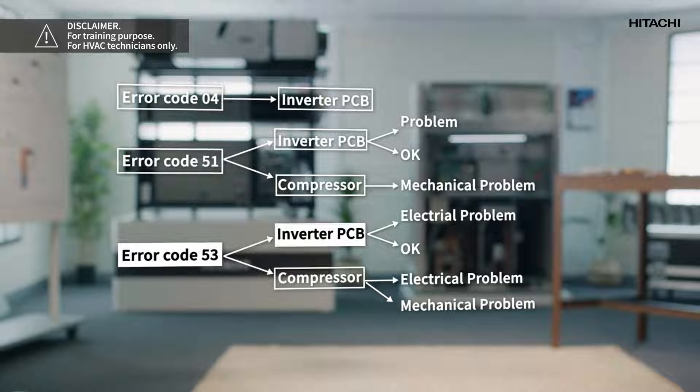Use the multimeter to check the output voltage of the PCBs to see if they are uniform. If the values are uniform, this means that the PCB is okay but there is a mechanical problem — you must change the compressor. If the values are not uniform, the problem is electrical — you must change the PCB.